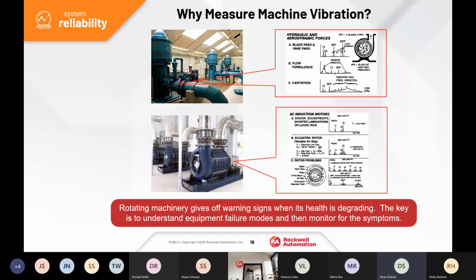Almost everybody I deal with has some sort of condition-based monitoring system that affects their reliability. They'll go around with a handheld data collector, a device with a little magnetic probe that gets stuck onto these pumps and motors, and it sits there for a few minutes recording the vibration signature. You could have vibration from a pump due to cavitation, from a pump-motor combination being misaligned, all kinds of things causing different vibrations. But these vibration signatures recorded by handheld devices are very specific to what's going on within those physical apparatuses, even the number of vanes on an impeller produces a very specific frequency.